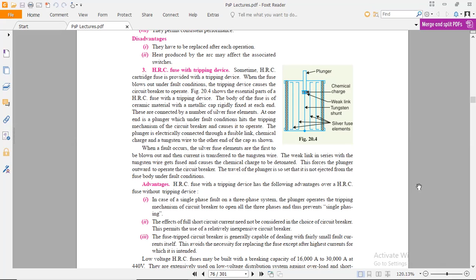The effect of full short circuit current need not be considered in the choice of circuit breaker. This permits the use of a relatively inexpensive circuit breaker. The fuse-tripped circuit breaker is generally capable of dealing with fairly small faults itself, thus avoiding the necessity of replacing the fuse except after the highest currents for which it is intended. So these are the further advantages of the tripping mechanism based HRC fuse.